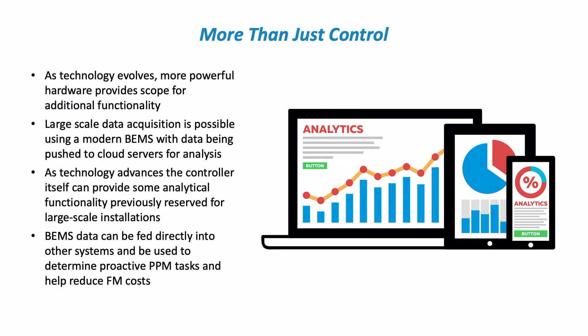BEMS data can also be fed into other systems to determine proactive PPM tasks — planned preventative maintenance. Typically you'd have a schedule to check a pump every three months, but with BEMS monitoring that pump, maybe we don't need to do it every three months. We can use analytical data to confirm the pump is running fine and extend that maintenance interval, making better use of time and reducing not only energy costs but facilities management costs as well.